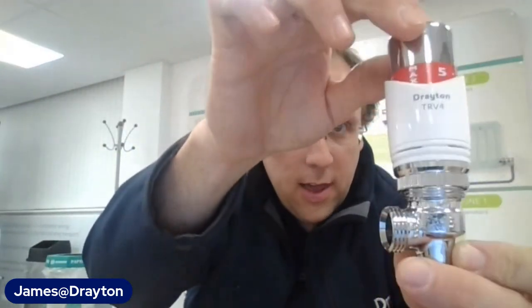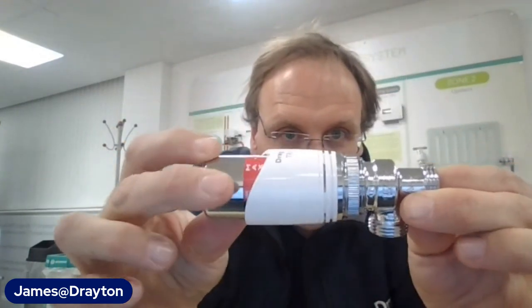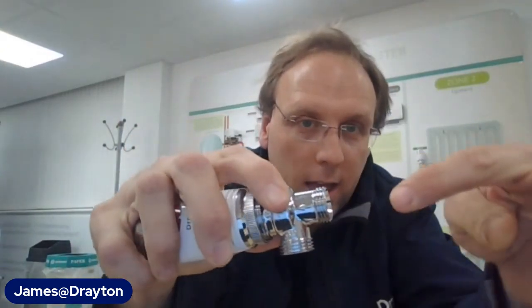So kick the heating on and establish which is the flow and return. These can go on either the flow or return, but if you want the sensing head to sit vertically, as we're sort of used to in the UK, then this has got to be on the flow side, because it's got to flow out of the floor and into the radiator. If you fit these on the return, which you can do, you've got to roll the head over and have the sensing head sat on its side so that the flow comes out of the radiator and back into the floor, respecting that flow direction arrow. So flow direction is a key one for these.